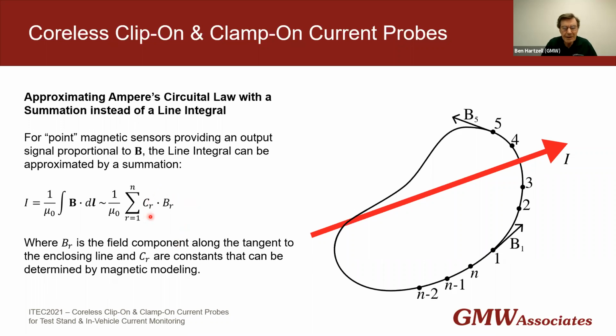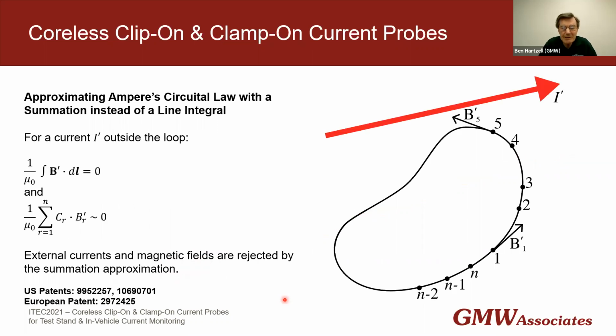And we make the approximation that the line integral is this summation, a coefficient times the measured field. And these coefficients are determined by some magnetic modeling, and it turns out that we get a result that can be within better than 1% in a wide range of applications. Now, it's important to note that if the current is outside this line, the circuital law would say that the line integral is going to be equal to 0 because there's no enclosed current. Similarly, the summation will be approximately 0. So by doing this summation, even though there are external currents and other magnetic fields, we get a very good rejection of the external fields and external currents.